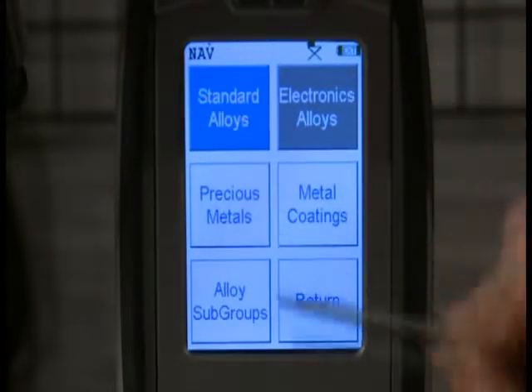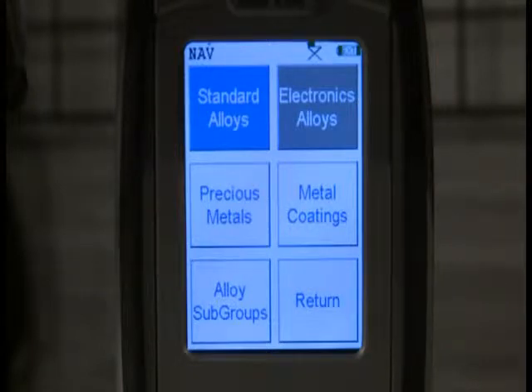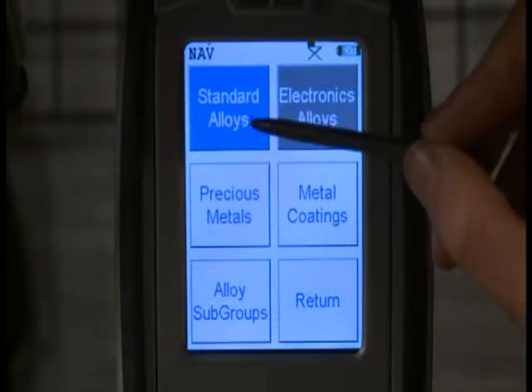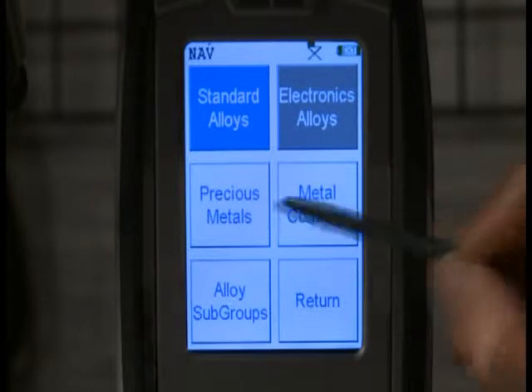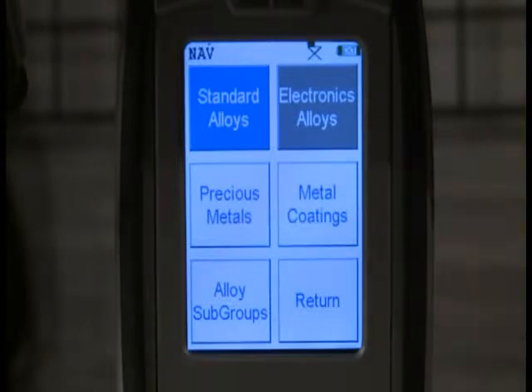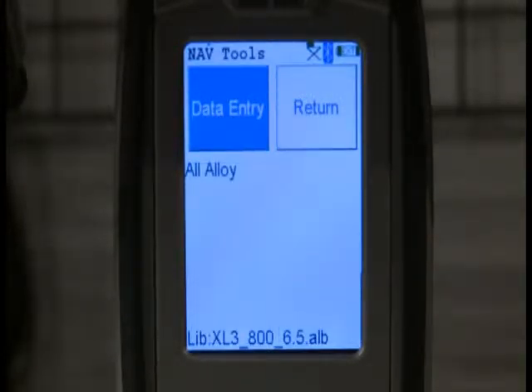Select the metals icon to bring up the available metal modes on which this instrument includes standard alloy, electronics alloy, precious metals, and metal coating. Some of the standard alloy subgroups are included but are not normally needed for PMI applications. For normal PMI work, select the standard alloy icon, which will take you to the data entry test screen where you are ready to begin testing. This is also where you will enter data if you choose to do so. You are now ready to verify your instrument's performance with your check sample.